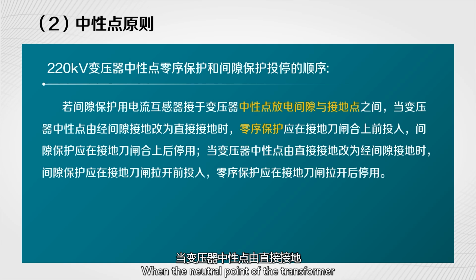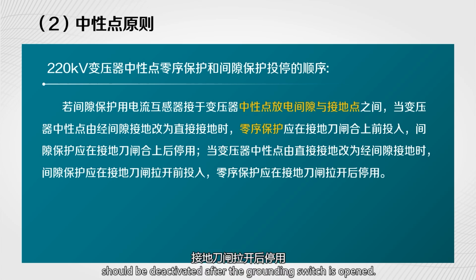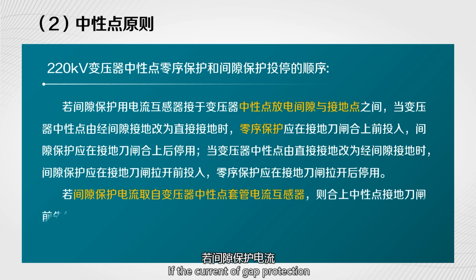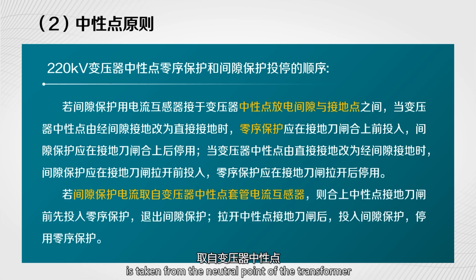When the neutral point of the transformer is changed from direct grounding to gap grounding, gap protection should be activated before the grounding switch is opened, and zero sequence protection should be deactivated after the grounding switch is opened. If the current of gap protection is taken from the neutral point of the transformer bushing current transformer, before closing the neutral grounding switch, first activate the zero sequence protection and then exit the gap protection. When the neutral grounding switch is opened, activate the gap protection and stop the zero sequence protection.